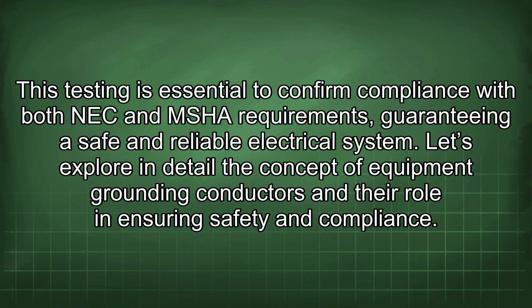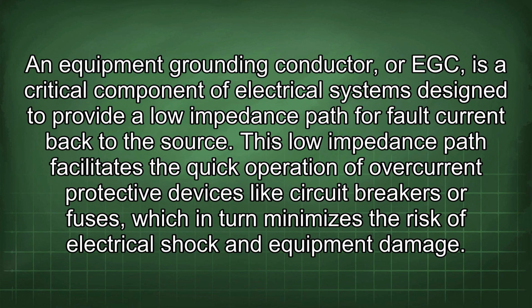Let's explore in detail the concept of equipment grounding conductors and their role in ensuring safety and compliance. An equipment grounding conductor, or EGC, is a critical component of electrical systems designed to provide a low impedance path for fault current back to the source. This low impedance path facilitates the quick operation of overcurrent protective devices like circuit breakers or fuses, which in turn minimizes the risk of electrical shock and equipment damage.